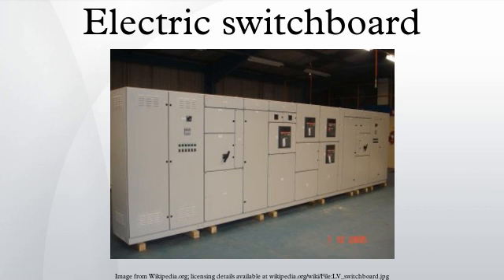Inside a switchboard there will be one or more busbars. These are flat strips of copper or aluminum to which the switchgear is connected. Busbars carry large currents through the switchboard and are supported by insulators.